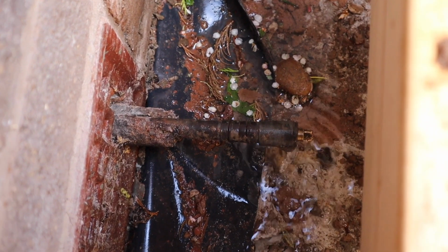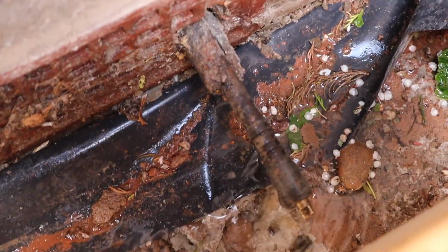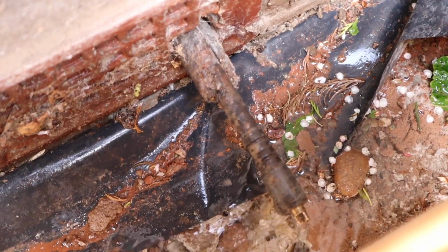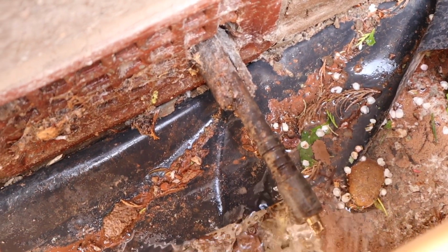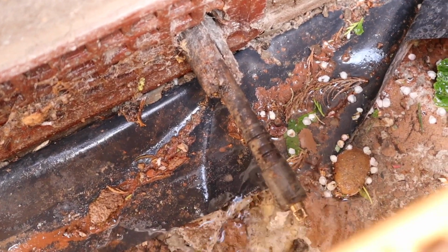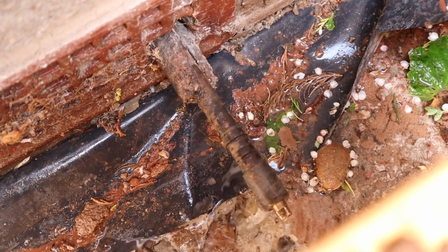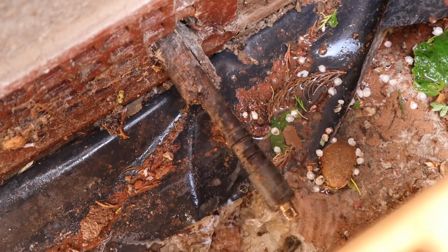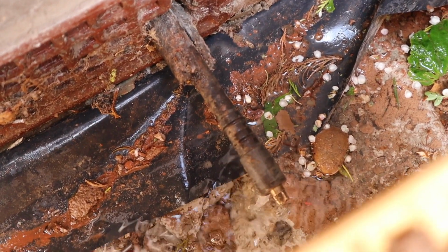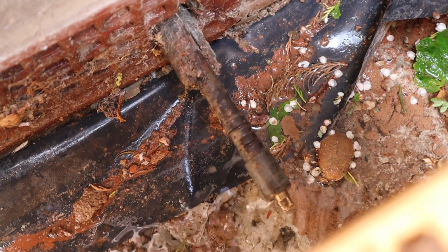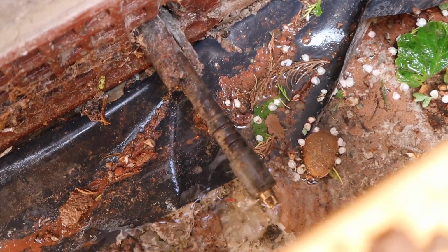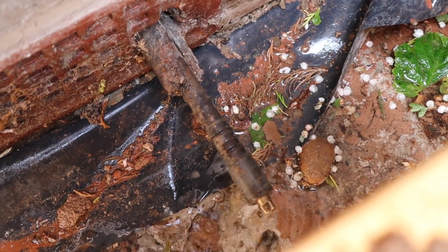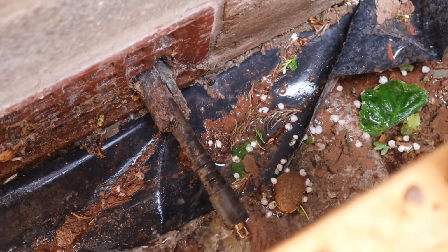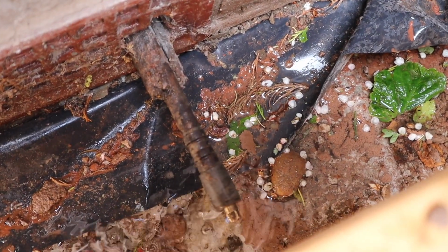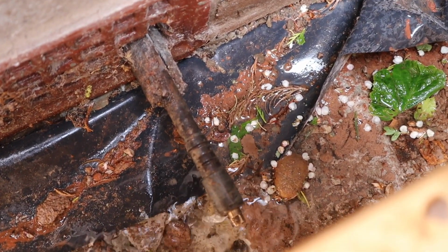Now I don't know if you can see this very well, but that's the drain coming out through the wall to drain the central heating system. And again, when I was an apprentice this was quite common, but obviously now it wouldn't be done because the drain is outside the envelope of the building and will actually freeze. But this is now into a new extension, which is going to be changed later anyway. But yeah, always look out round the outside of a 50s built house and see if there's a drain sticking out of the wall, because it'll be for the central heating.